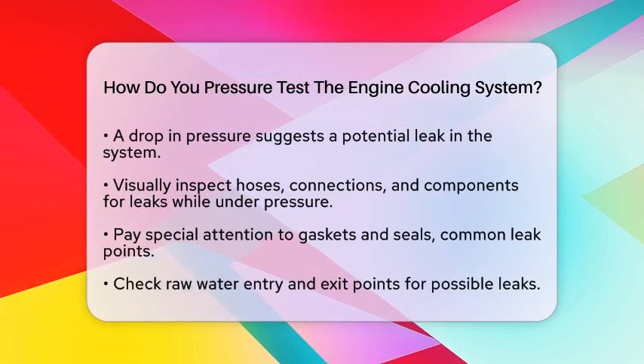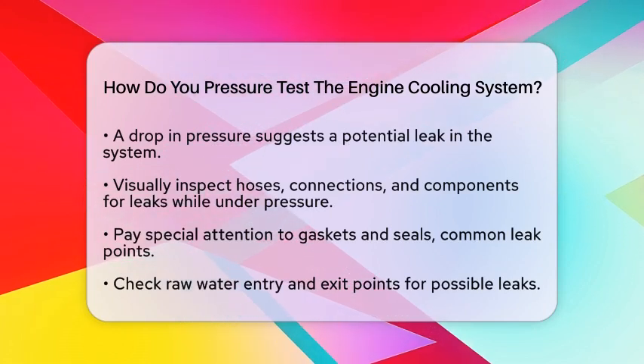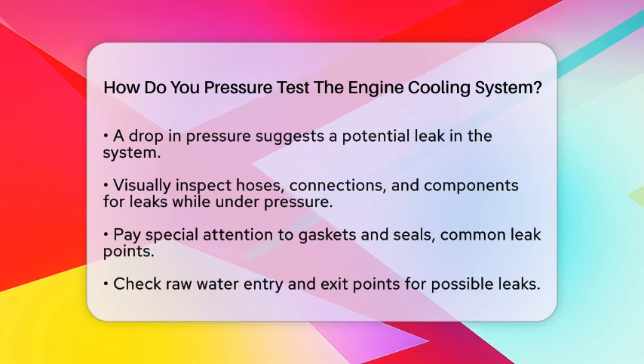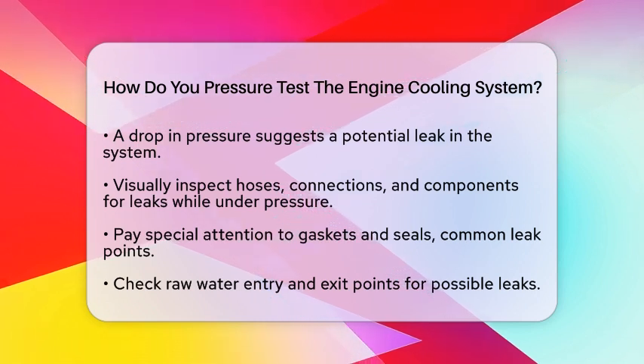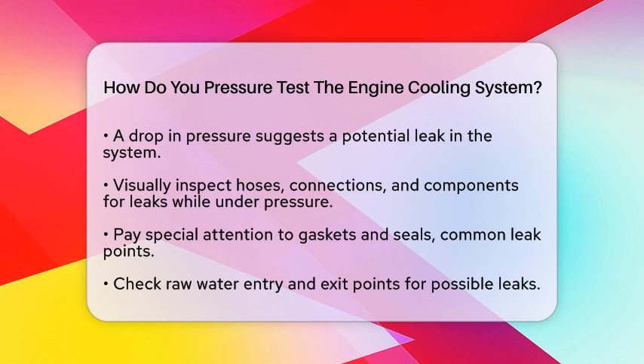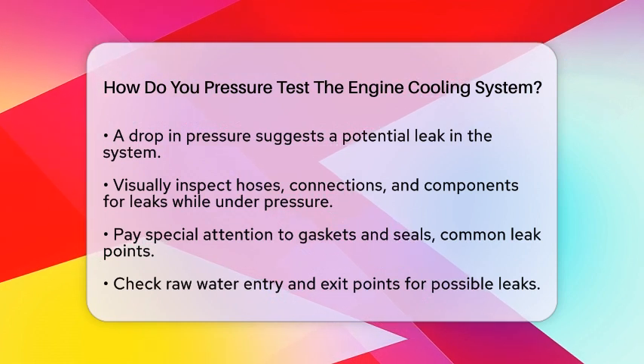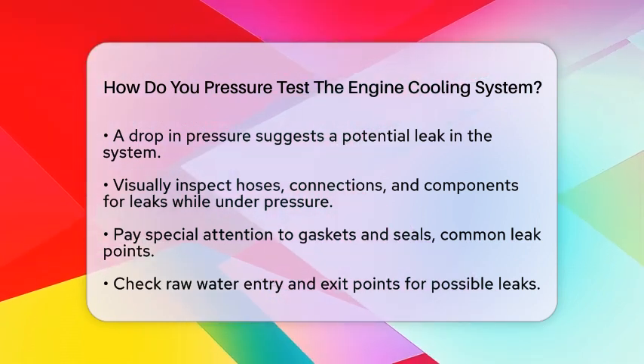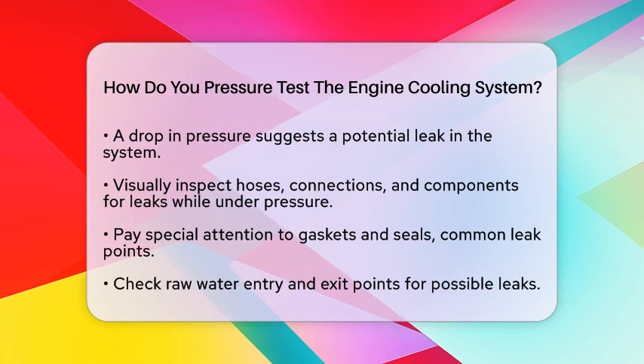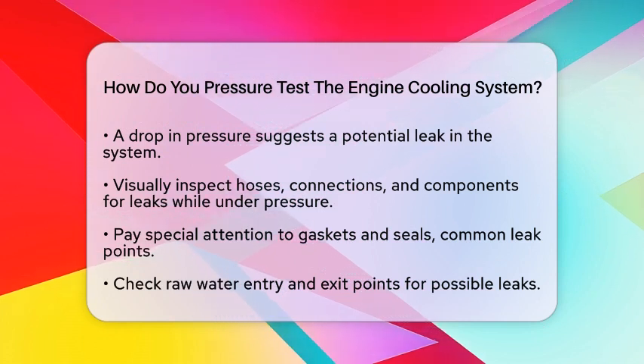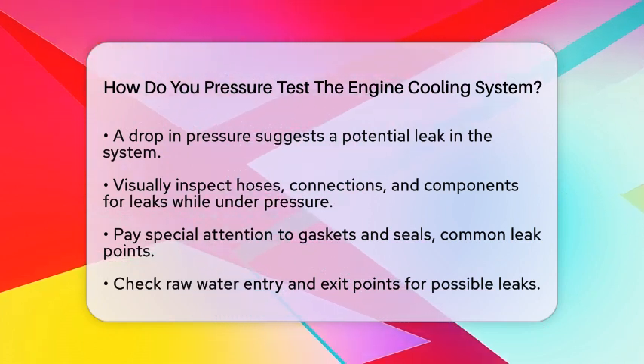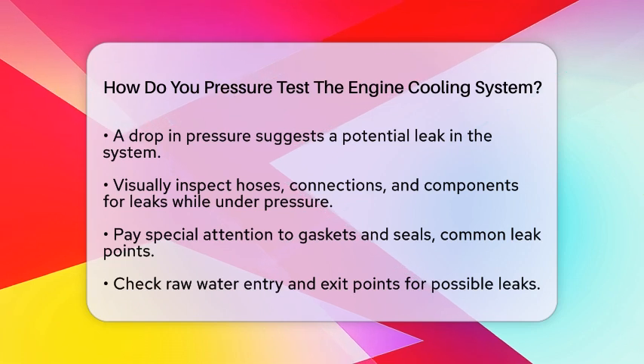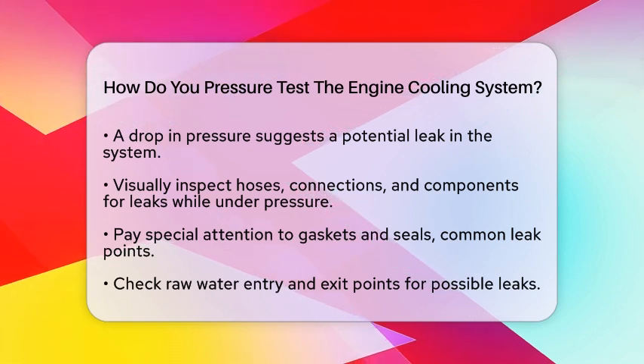While the pressure is applied, visually inspect all hoses, connections, and components like the water pump and heat exchanger. Pay close attention to gaskets and seals, as these are common areas for leaks. In addition, check where raw water enters and exits the system. Leaks in these areas can lead to seawater entering the engine or coolant leaking into the bilge.